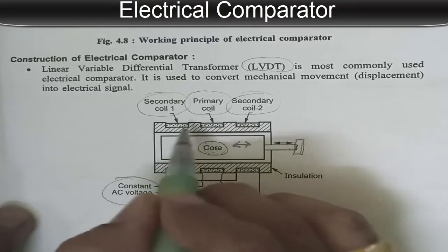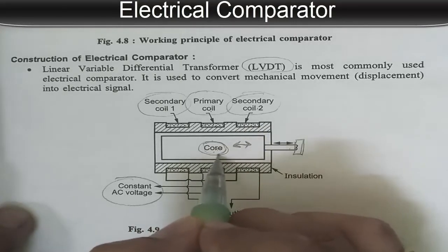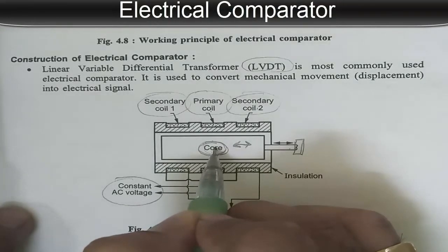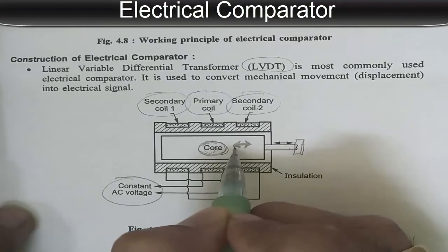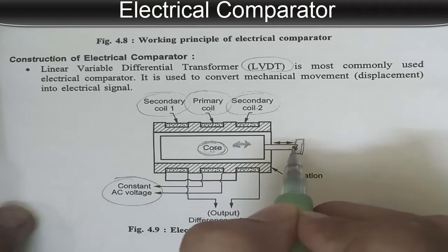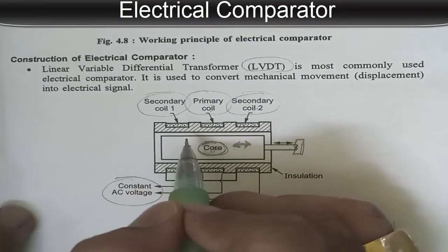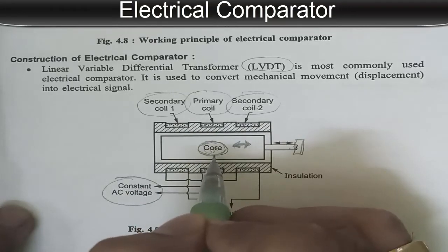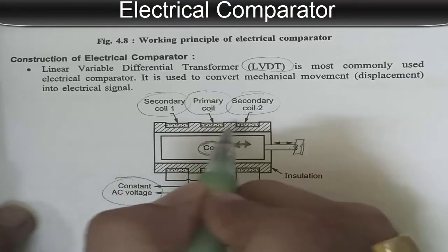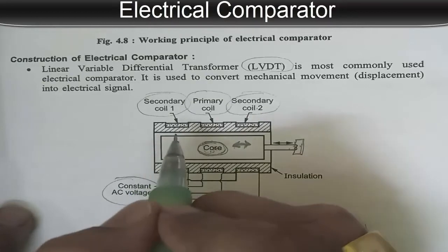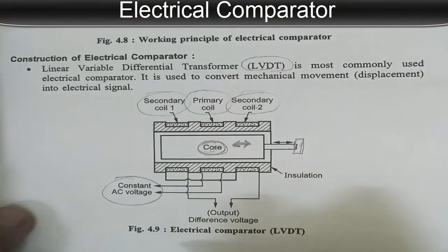When the core is at the middle position, the voltage induced in both secondary coils is the same and out of phase, which gives the net output result as 0. Now, when the core moves right or left even a small distance — and this core is connected with the plunger — a differential voltage appears across the secondary coils in series, which is further calibrated in terms of the linear movement of the core or plunger. With this difference of voltage, we can easily find out the distance moved by the core.